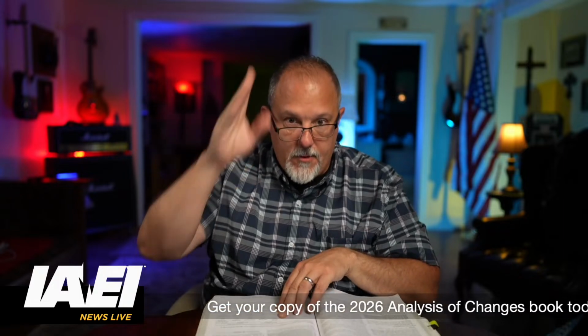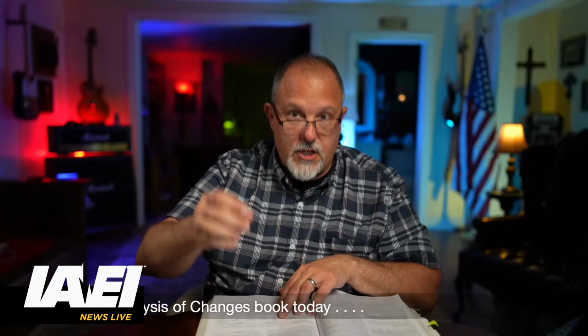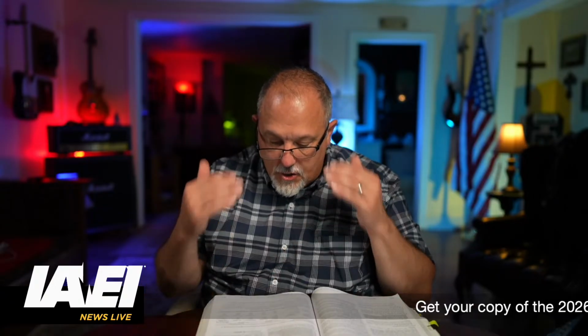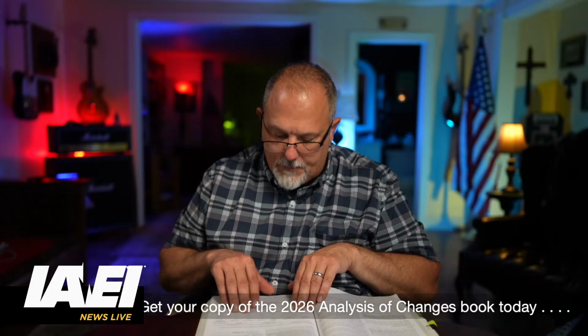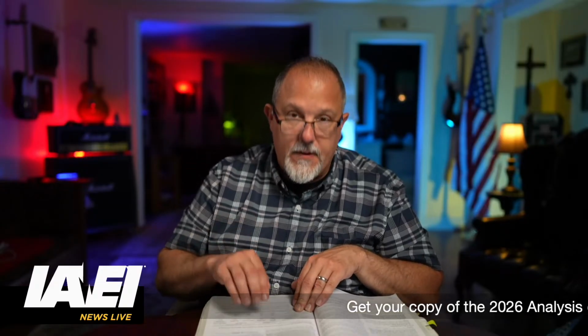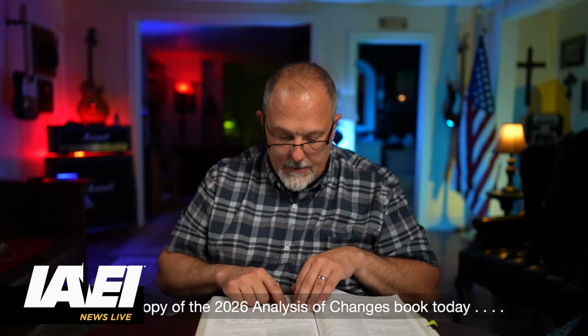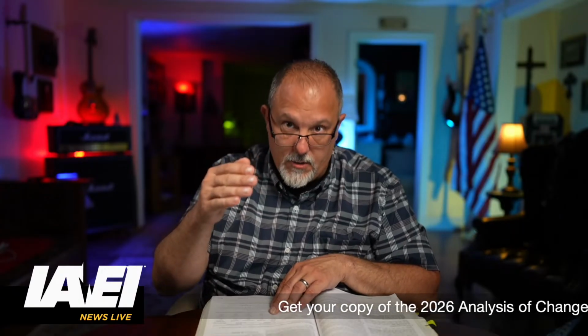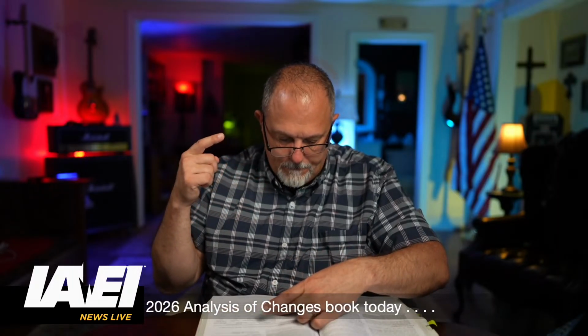I'm going to be applying 450.3a for protection of this transformer. And remember, the primary protection gives me my short circuit protection for the transformer. My secondary protection is going to give me my overload protection. The only place I don't have to have secondary protection is in supervised locations only on medium voltage applications, and for any impedance when my primary circuit breaker is at most 300%, and again I can go to the next larger based upon the commercially available, 300% and 250% on fuses.